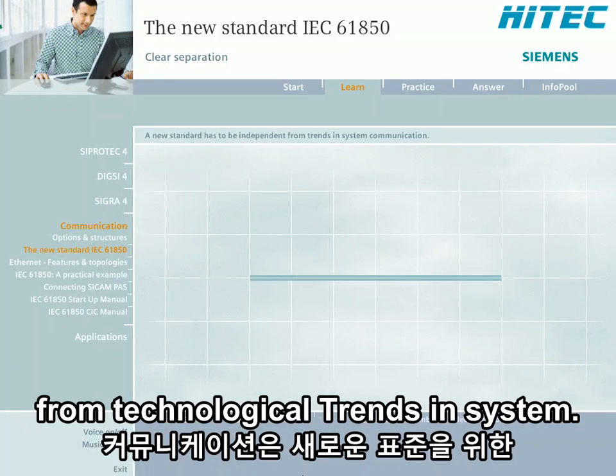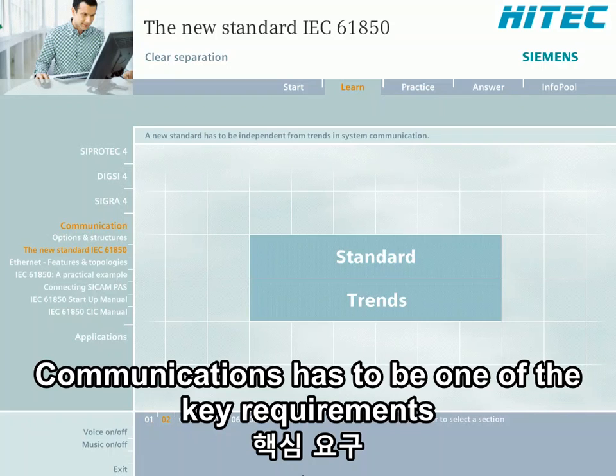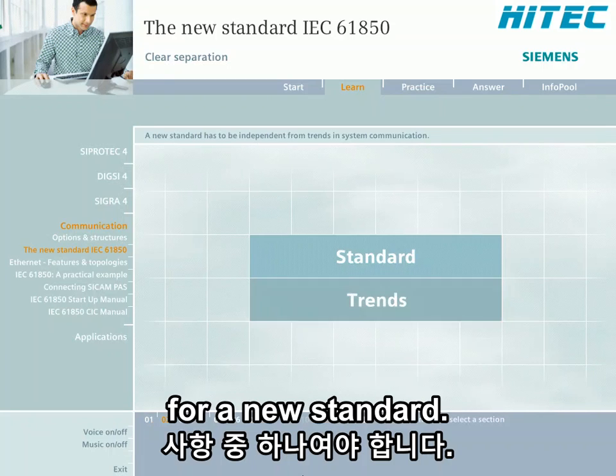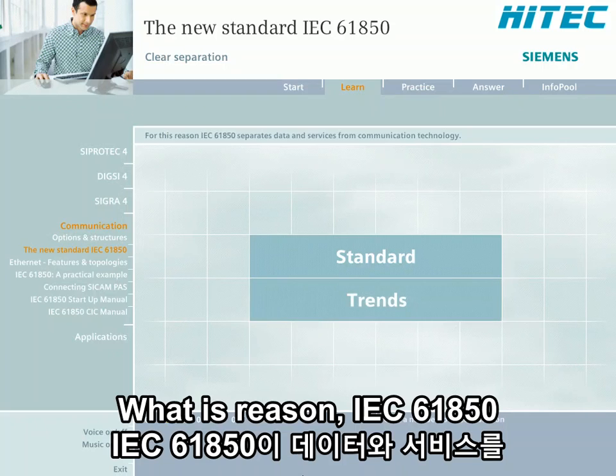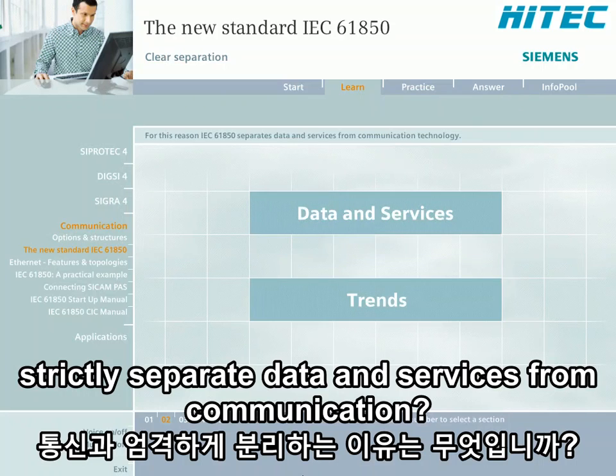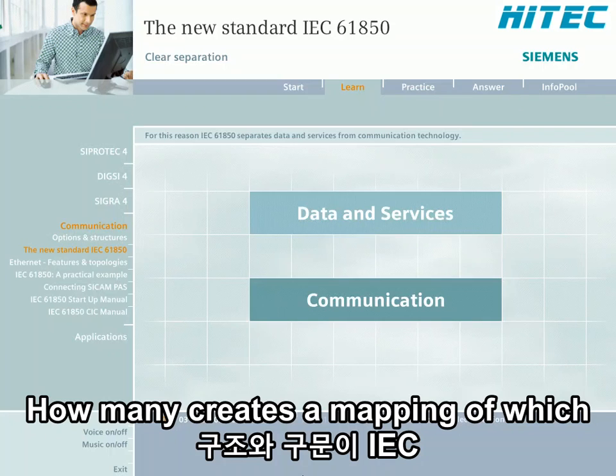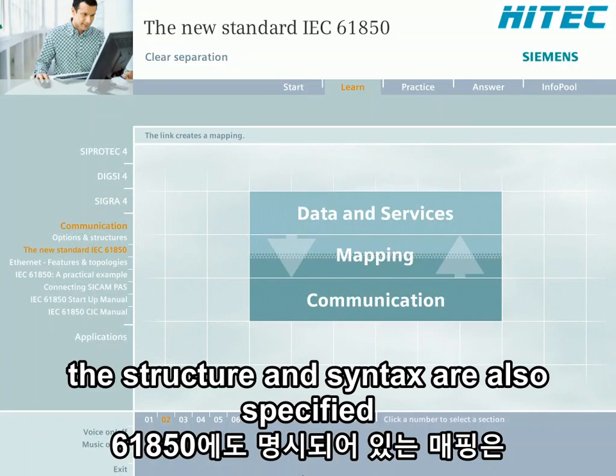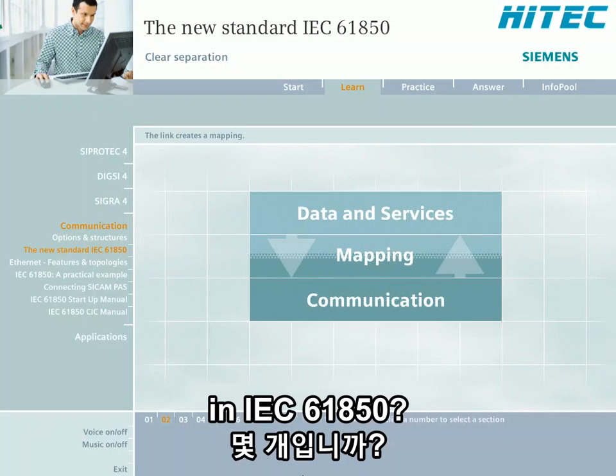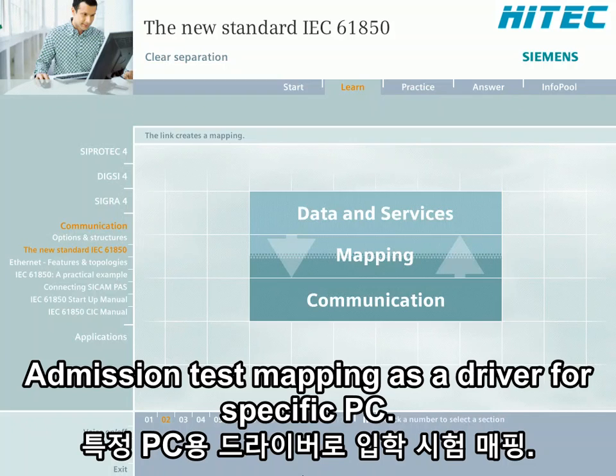Independence from technological trends in system communication has to be one of the key requirements for a new standard. For this reason, IEC 61850 strictly separates data and services from communication technology more than any other protocol. The link creates a mapping of which the structure and syntax are also specified in IEC 61850. Envision this mapping as a driver for specific PC peripherals, such as a printer.